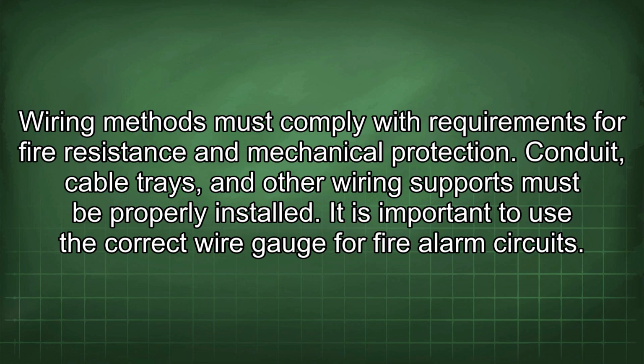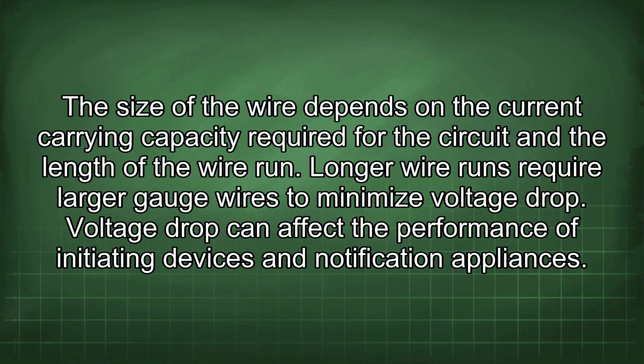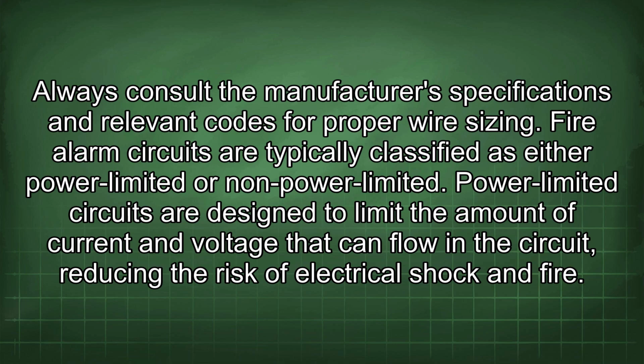It is important to use the correct wire gauge for fire alarm circuits. The size of the wire depends on the current carrying capacity required for the circuit and the length of the wire run. Longer wire runs require larger gauge wires to minimize voltage drop. Voltage drop can affect the performance of initiating devices and notification appliances. Always consult the manufacturer's specifications and relevant codes for proper wire sizing.